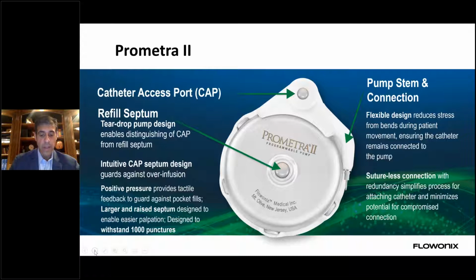There's positive pressure upon accessing the refill port, again 22.5 psi in the reservoir. So if you've ever accessed it, make sure you have a syringe attached, otherwise drug will shoot across the room. The positive pressure of the 22.5 psi also gives us some reassurance during the refill that the needle is still in the pump, as most pocket fills don't normally occur during the refill as the needle comes out of the pump. So while I'm refilling a pump, usually I push about 5 mLs of drug and let the syringe basically fill up a little bit, and I push 5 at a time to make sure I'm still pushing against this 22.5 psi, making sure all the drug is going in the pump.